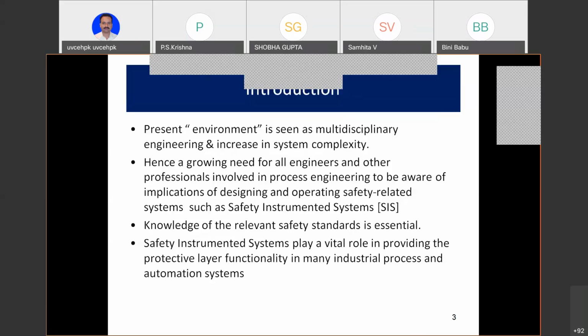Right. So that is a safety instrument system. Knowledge of relevant safety standards is essential. I labeled all the standards for you which are important for you to know. Safety instrument systems play a vital role in providing protective layer functionality in many industrial process systems. Now let us talk about this protection layer. It's like the security people, they've got tier 1, tier 2, tier 3, which you're all familiar with. The security system we are talking about is, as far as the plant is concerned, the core is the plant. The first level is by manipulating valves and looking at alarms and looking at mechanical devices which are not instruments. Then we have to manage the plant. And then if that is not possible, we go to a BPCS. And after that, if that is also not possible, we go to the safety instrument system. And even that goes on. That's what this protective layer LOPA is about.